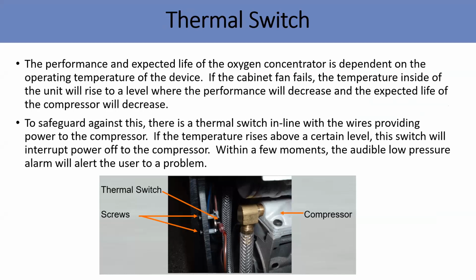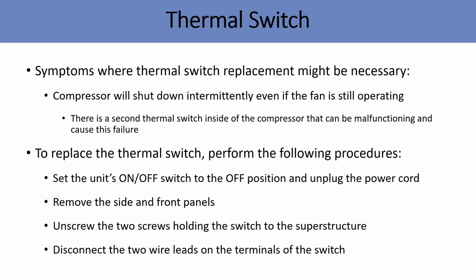The thermal switch is one of the important parts inside the oxygen concentrator. If the fan inside the oxygen concentrator is not working properly, or something is wrong with your compressor, this thermal switch is going to trigger and power off the compressor. So this is like a protection for your system. It ends up giving you a low pressure alarm because the compressor has stopped working, even though the fan inside the oxygen concentrator is turning. The compressor fails to work due to the thermal switch failing. Sometimes the thermal switch breaks because of a high surge and fails to work. So you need to replace the thermal switch. This is how you replace your thermal switch, the method of doing it, the procedure.